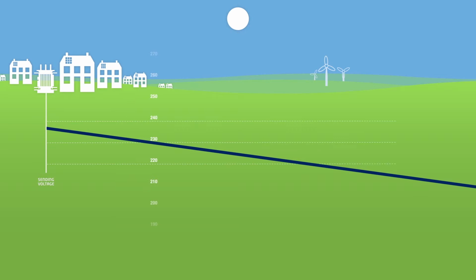Low-voltage networks operate within a set range, the statutory voltage range at which we must deliver electricity to our customers. To achieve this, the sending voltage at the substation is set high enough so that the voltage at the farthest point from the substation is within the required range. But this means that voltage at the end of the circuit is lower than the voltage closest to the substation.